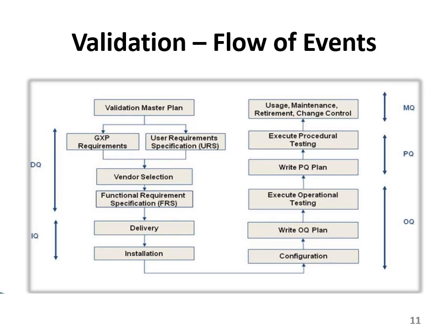Now next is installation qualification, which is IQ. In that, the first step is delivery, that the vendor has delivered the instrument to you, and then installation, where the instrument or equipment is installed in your laboratory. We will be discussing these all in detail later on, but right now, just to have a clear picture of the validation events, the flow of events, we are discussing this diagram.